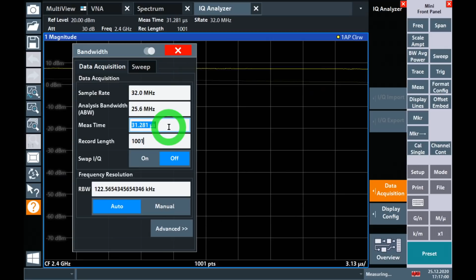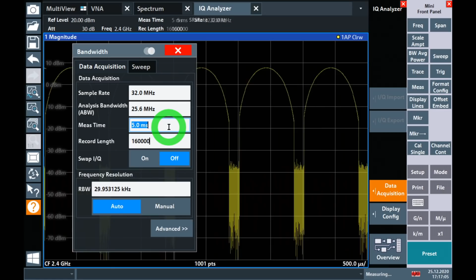We're not going to get into all the advanced functions here. All I want to do is increase the duration that the signal is captured to 5 milliseconds, and the instrument will adjust everything else automatically. Now right off the bat, we can clearly see that there is indeed a repetitive behavior, and the amplitude of the signal is changing over time. But it doesn't look very good because we're not triggering it. Let's go ahead and trigger this. We can trigger on IQ power. Let's trigger on something, let's say minus 25 dBm over here. There you go.